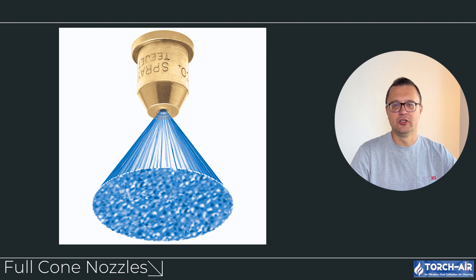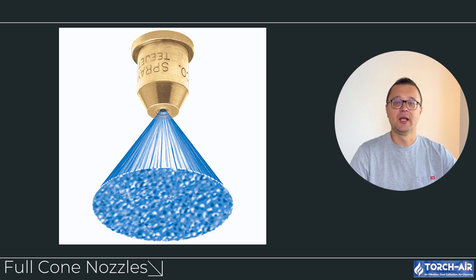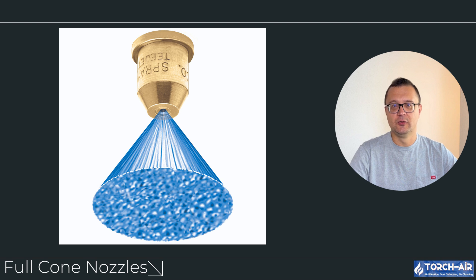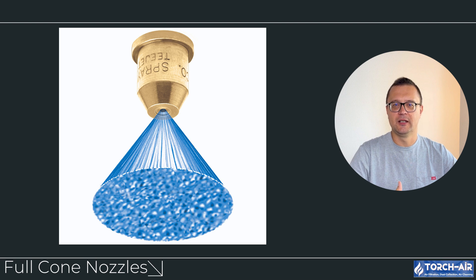Let's explore the most common nozzle types used in scrubbers. Full cone nozzles are designed to spray the scrubbing liquid in a full cone-shaped pattern, creating a uniform distribution of droplets over a large area. These nozzles are highly effective for applications where thorough gas-liquid interaction is needed, and are best for applications requiring high liquid flow rates and uniform droplet distribution. They are excellent for large-scale scrubbing operations, particularly in gas absorption applications like removing sulfur dioxide (SO2) or hydrogen chloride (HCl). Consideration: they require higher pressure to maintain consistent spray patterns, which could lead to increased energy consumption.